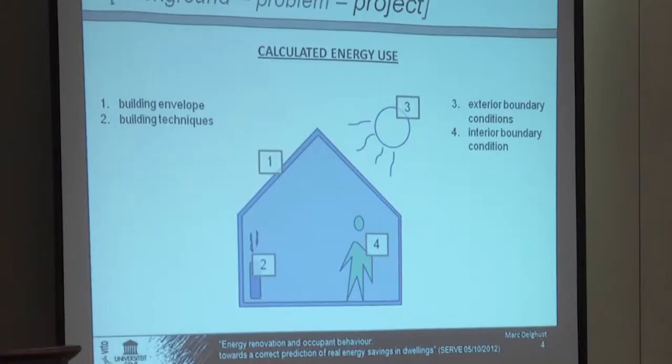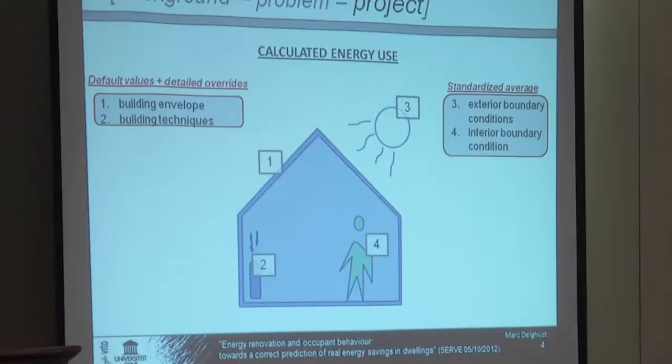The background project is actually looking at the calculation method. Those ISO standards start from a heat balance in houses. The heat balance energy use is actually a simple idea — you have four main parameters: the building envelope and building techniques; the exterior boundary condition (weather, sun, temperature); the interior boundary condition (set point temperature, internal heat gains, and so on). That is all within the calculation model, but to make it efficient we use default values, sometimes overwritten with detailed values — standardized averages, standardized climates, standardized user behaviour, and so on. That's the first cause of discrepancy.